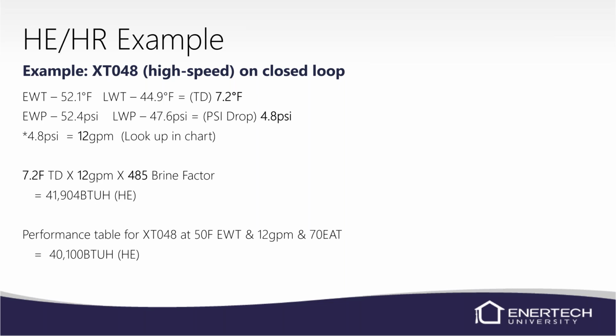So we take our entering water pressure next. I don't care if you take pressure drop first or temperature difference, it doesn't really make any difference. But here we're doing pressure drop second. So we've got 52.4 in, we're leaving at 47.6. So we just do the math and that gives us 4.8 PSI. So I'm going to tell you that once we look it up in the chart, that's going to tell you that it's 12 GPM. So we've got the numbers that we need.